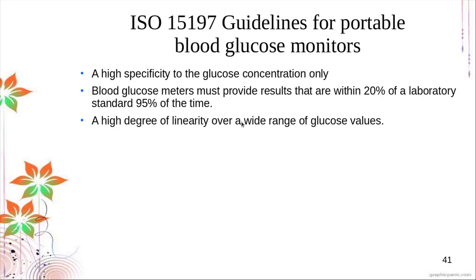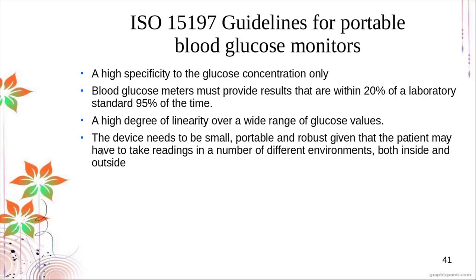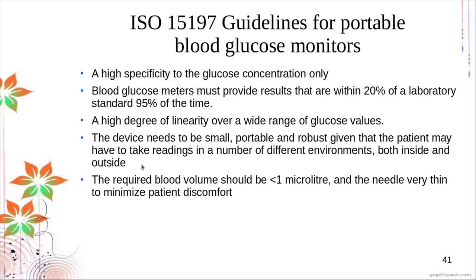The third requirement is a high degree of linearity over a wide range of glucose values, because measurement is made through calibration and fitting over a curve. Good linearity is needed for proper calculation of the measurement signal versus the calibrated measurement. The device also needs to be small, portable, and robust, as patients may take readings in many different environments. The required blood volume should be less than 1 microliter and the needle very thin.